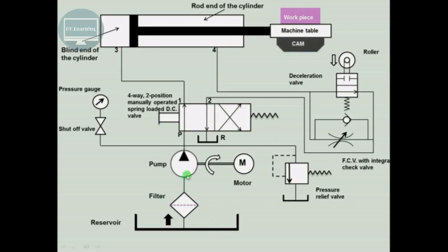The other components of this hydraulic circuit are as usual. We have the reservoir; from the reservoir the fluid enters the filter and gets filtered. When the pump is driven by the electric motor, the fluid is pumped from the reservoir. There is a four-way two-position manually operated spool direction control valve with two positions: left envelope and right envelope. Port P is the pump port, R is the reservoir port, and ports 1 and 2 lead to the blind end and rod end of the cylinder respectively. From port 3 fluid enters the blind end of the cylinder, and from port 4 it goes to the reservoir.